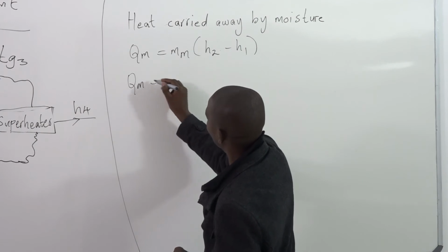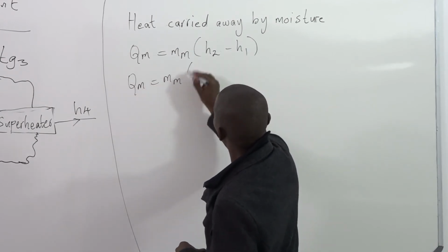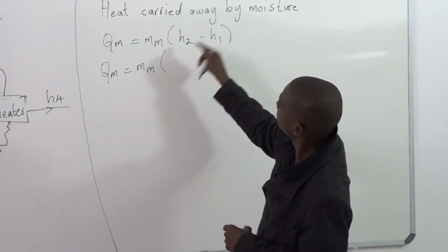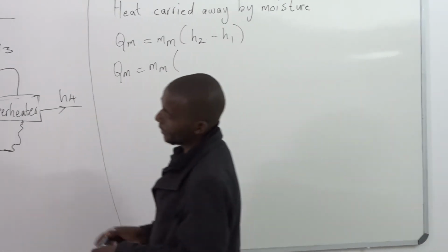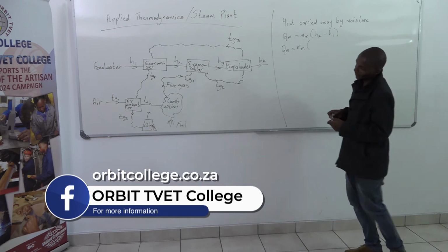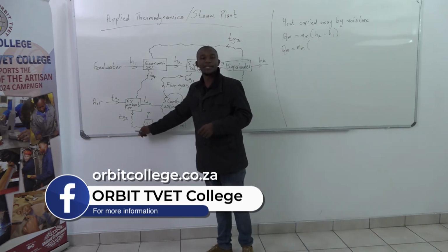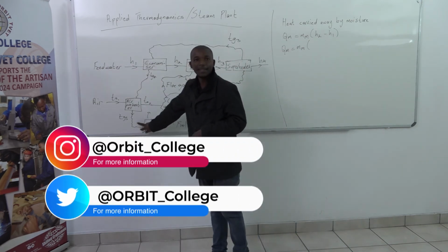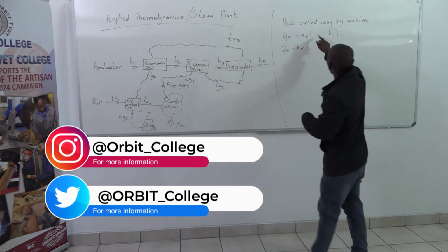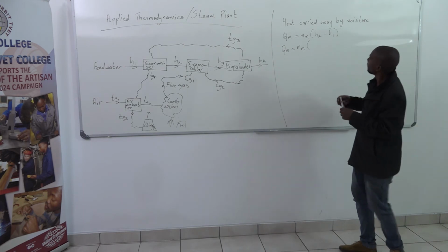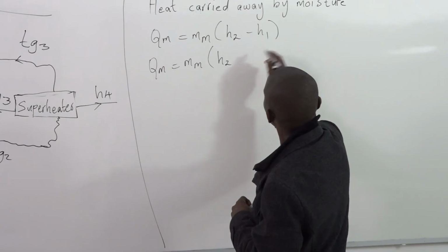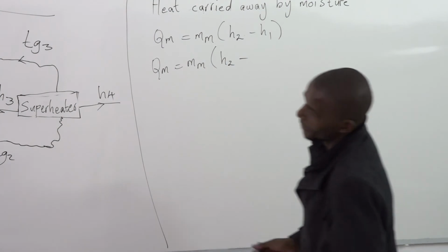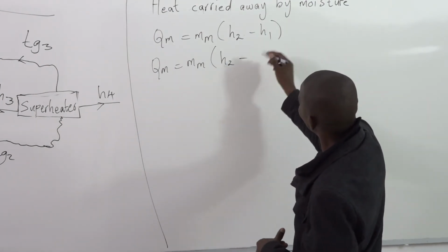QM, heat carried away by moisture, is equal to mass of moisture into H2. This H2 is the final enthalpy of moisture, which you can get from the steam tables. Depending on the temperature and pressure of the moisture at the chimney base, you just read from the steam tables. If you're given the final temperature of the moisture and the pressure at the chimney base, you can just read this off from steam tables. This H2.